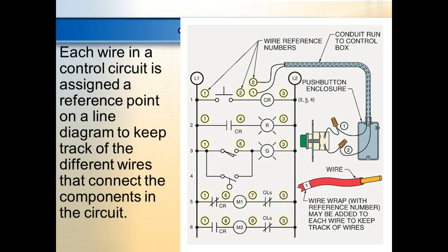Now ours is pretty easy because we've got a diagram of the device on the right hand side. It shows us the numbers that belong to the contacts and what belongs to the coils. You understand that? So what I do when I start wiring this thing up is I say, well, I need a normally open contact on CR or normally closed contact on CR. I'll look at my diagram and say, okay, where's the normally closed contact? Well, it's in between numbers 1 and 6. And then I'll write this on my diagram. And then when I wire it up, I'm not trying to figure out where the normally closed contact is anymore. I'm just saying, well, that wire goes to number 1 on CR. Does that make sense? So what we do is we come up here and we do these manufacturer numbers.